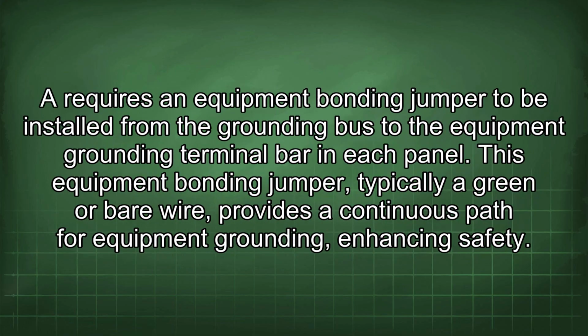Fourthly, regarding the location of equipment bonding jumpers, NEC section 250.110 requires an equipment bonding jumper to be installed from the grounding bus to the equipment grounding terminal bar in each panel. This equipment bonding jumper, typically a green or bare wire, provides a continuous path for equipment grounding, enhancing safety.